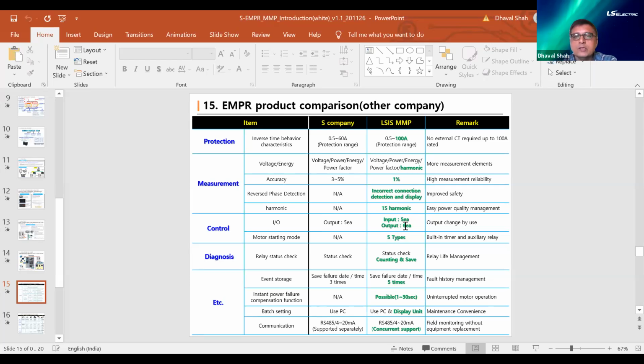IOs are there, yes, of course. 5 input and 6 output IOs are there. So again, you can configure as per the need. Starting method, five types of starting methods are there, which we already learned: DOL, star delta, and various operating mechanisms. Diagnosis, you can have counting and saving. You can have the status check of the relays also. And of course, as we discussed earlier, event storage, 5 times of the storage is possible. And instantaneous power failure, you have the time settable, so you can set the time accordingly. Communication is also there. RS485 and 4 to 20 milliamps output is available.